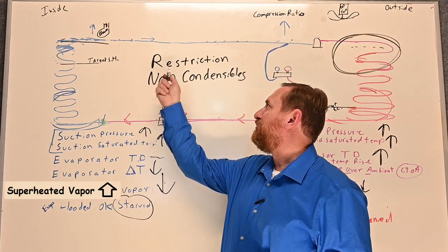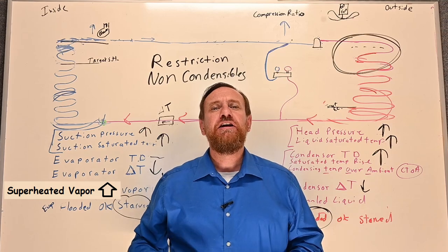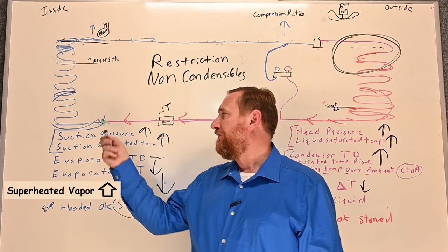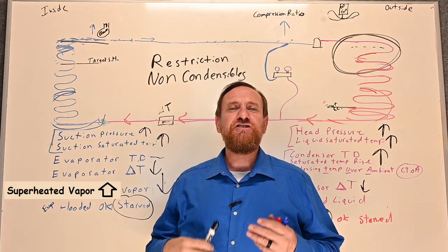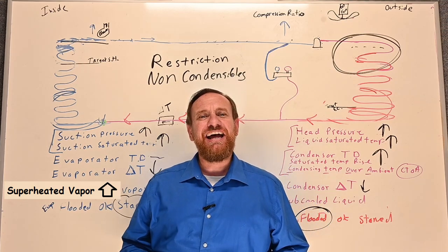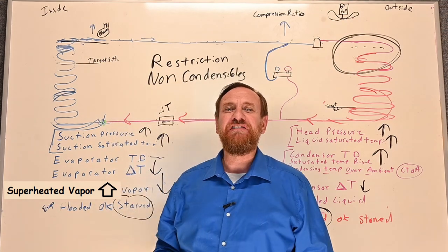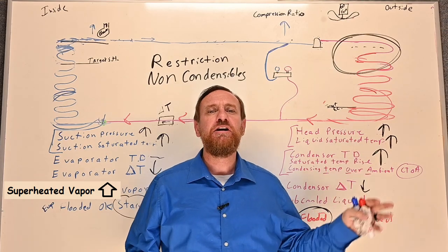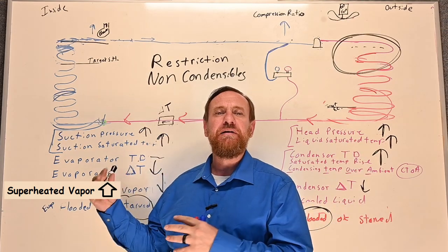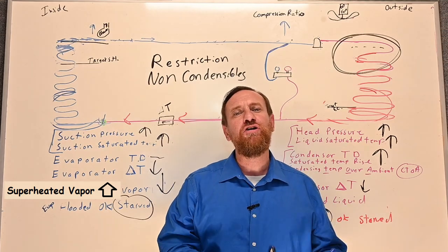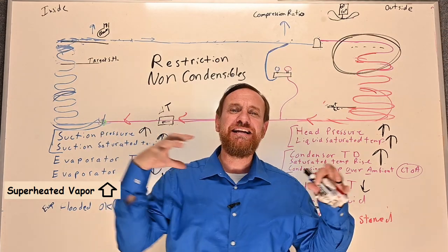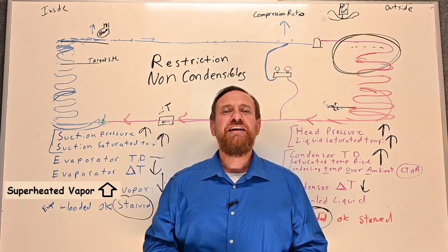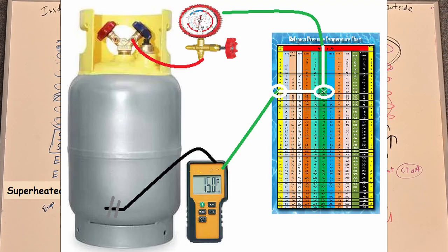Since the symptoms are very similar between a restriction and non-condensibles — you can check delta T across the filter dryer or at different spots on the liquid line — but if the restriction is at the metering device, a lot of times you just have to open it up. If we have to open that metering device anyway, that means we have to recover all the refrigerant from the system regardless.